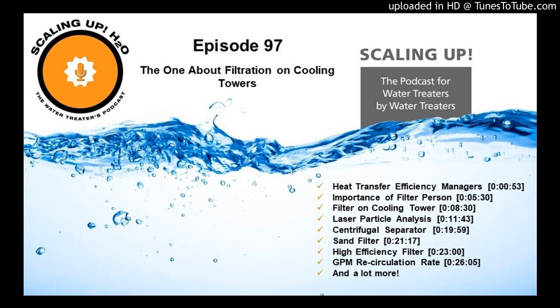than centrifugal separators. And because those larger particles produce a lot of the turbidity appearance in cooling water, the water looks a lot better when you put a traditional sand filter on. And that traditional sand filter removes a significant amount of particulate. There's no question about that.